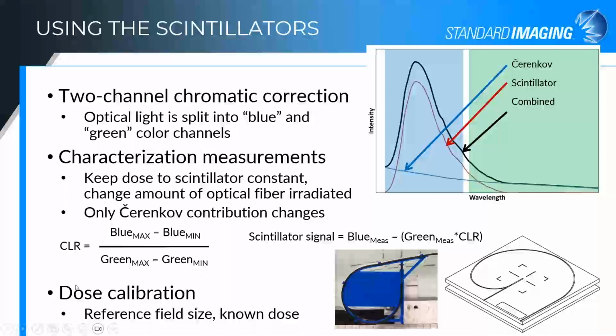If you want to do a dose calibration for your scintillator, you give it a known dose and a reference field size, and that just becomes a constant multiplicative factor to do that unit conversion, really, between the scintillation signal, corrected scintillation signal, I should say, and the dose.